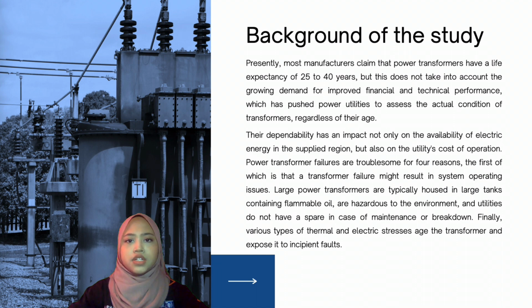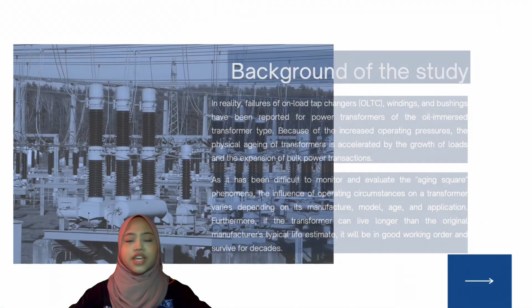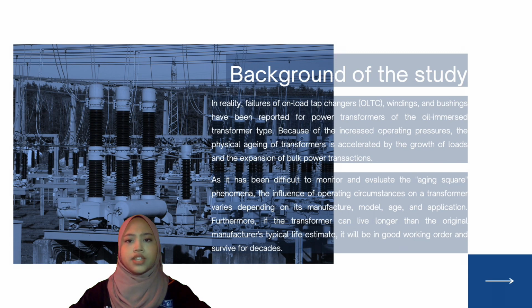Finally, various types of thermal and electric stresses age the transformer and expose it to incipient faults. In reality, failures of on-load tap changers, windings, and bushings have been reported for power transformers of the oil-immersed transformer type. Because of the increased operating pressures, the physical aging of transformers is accelerated by the growth of loads and the expansion of bulk power transactions. It has been difficult to monitor and evaluate the aging phenomena. The influence of operating circumstances on a transformer varies depending on its manufacture, model, age, and application. Furthermore, if the transformer can live longer than the original manufacturer's typical life estimate, it will be in good working order and survive for decades.